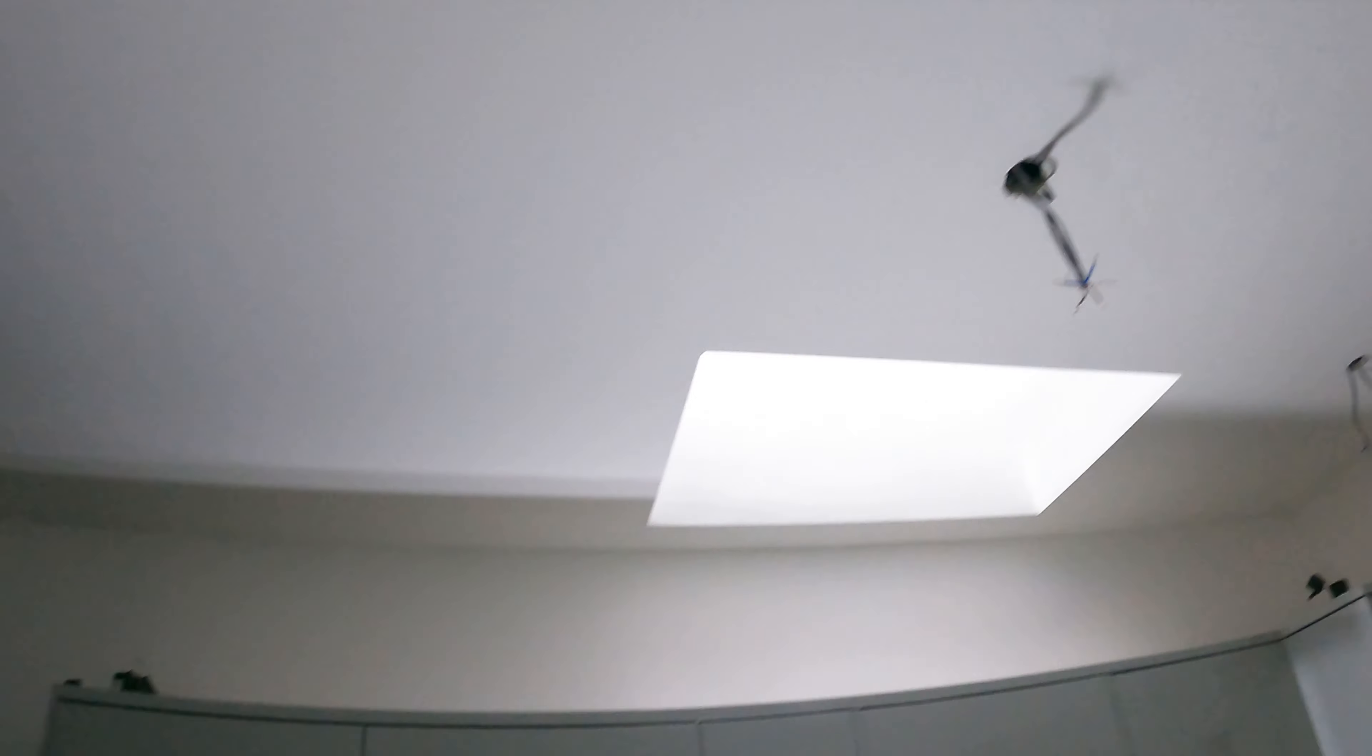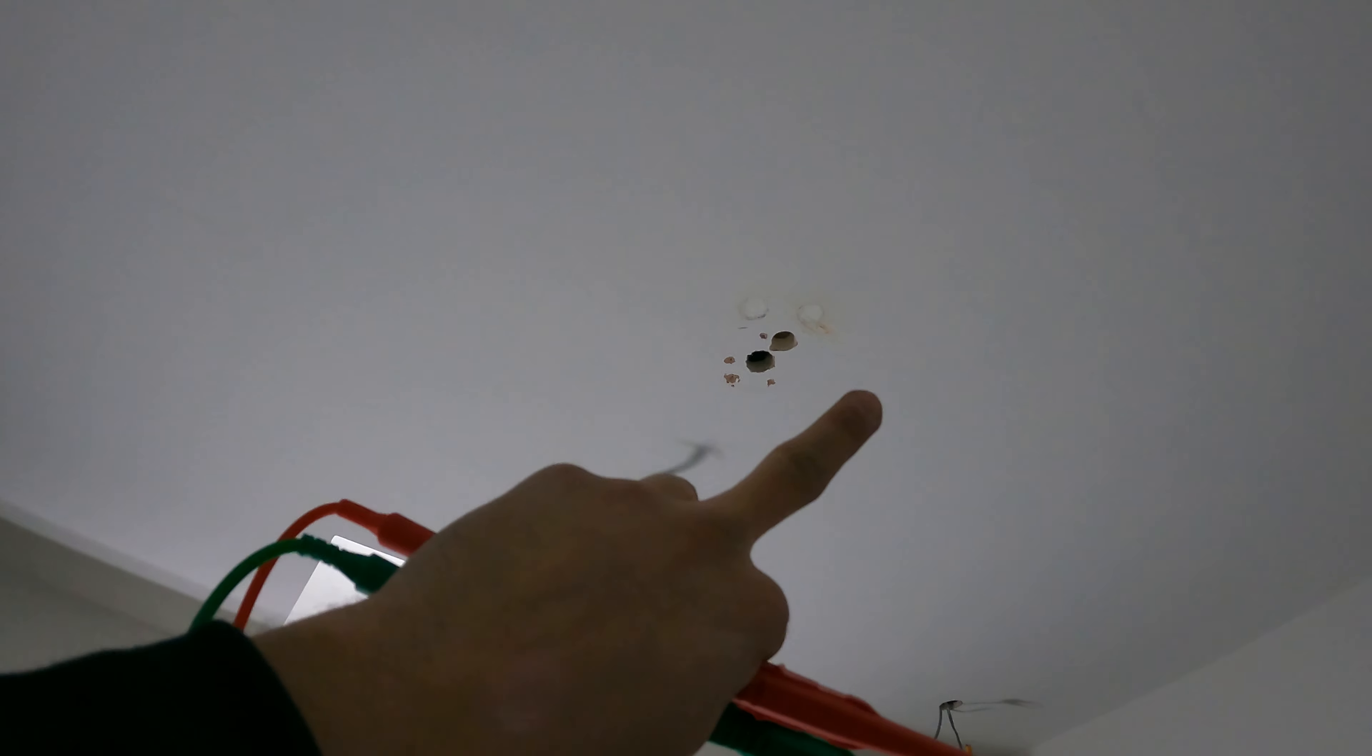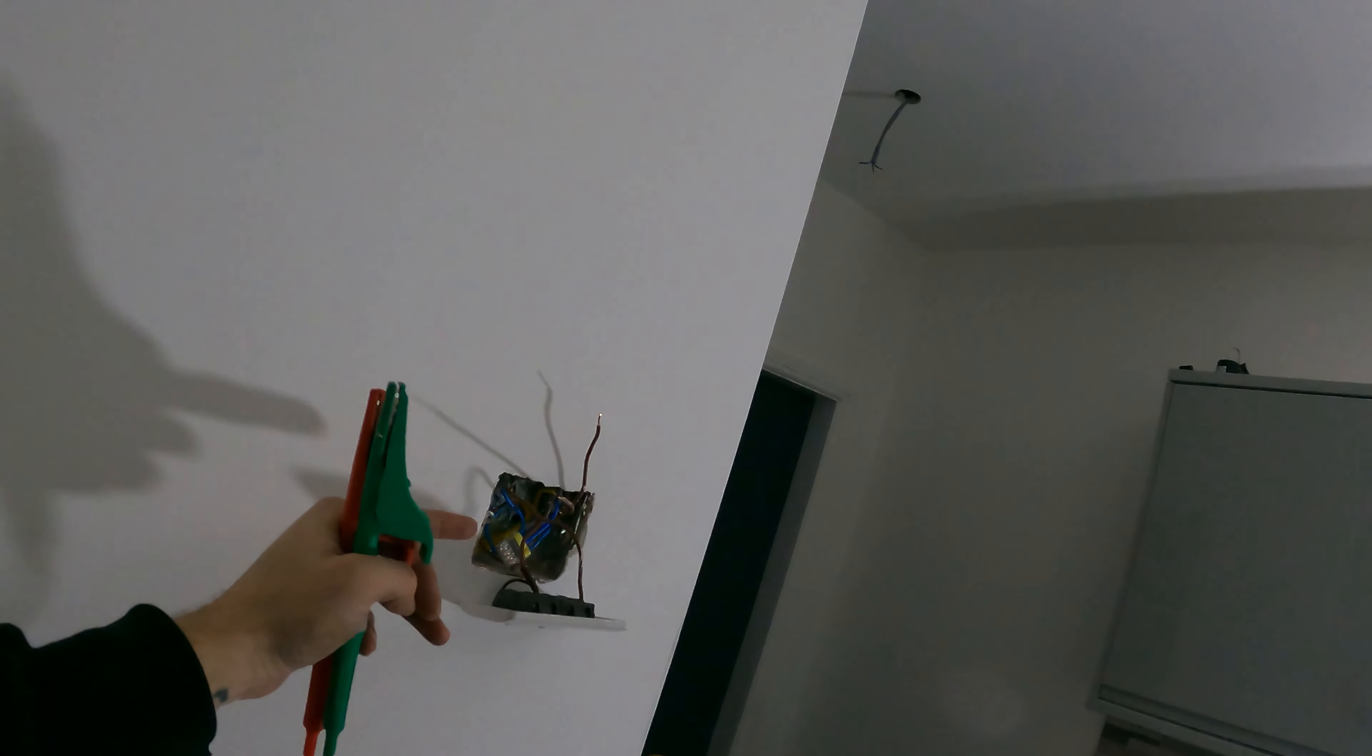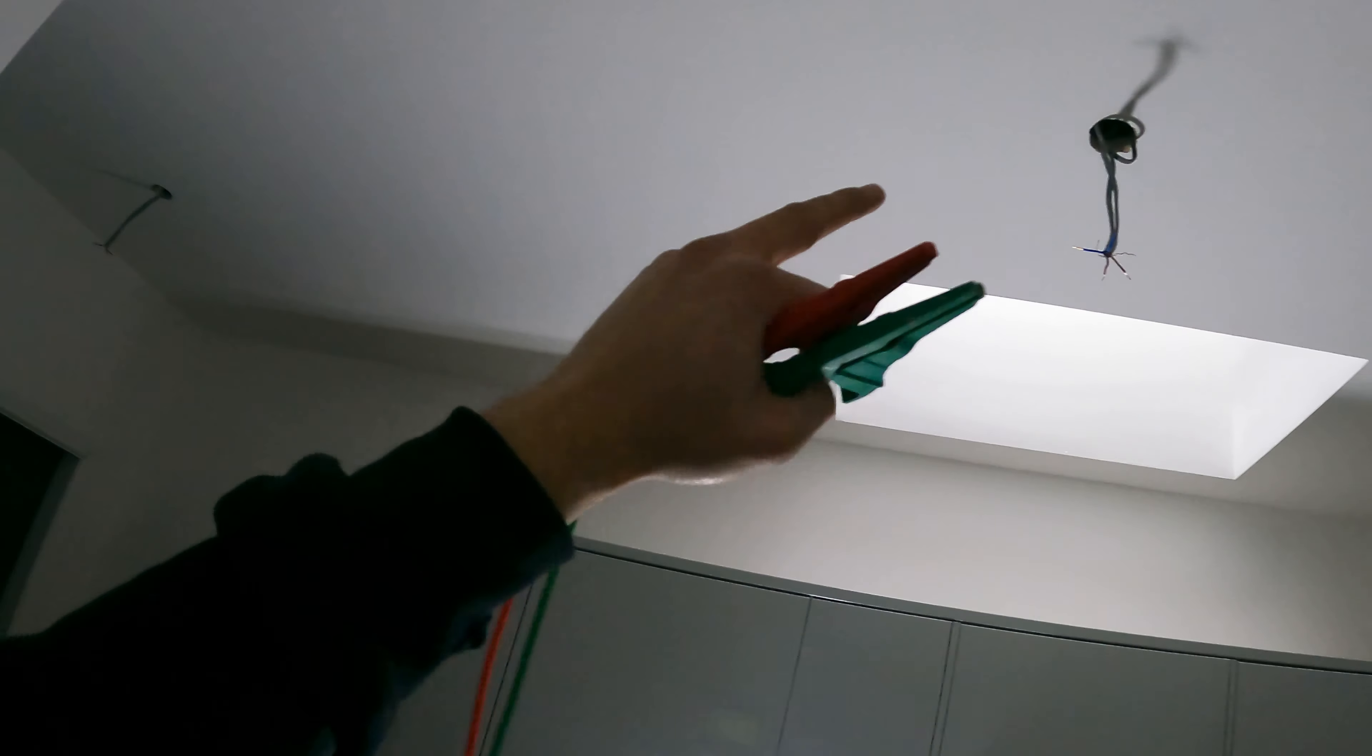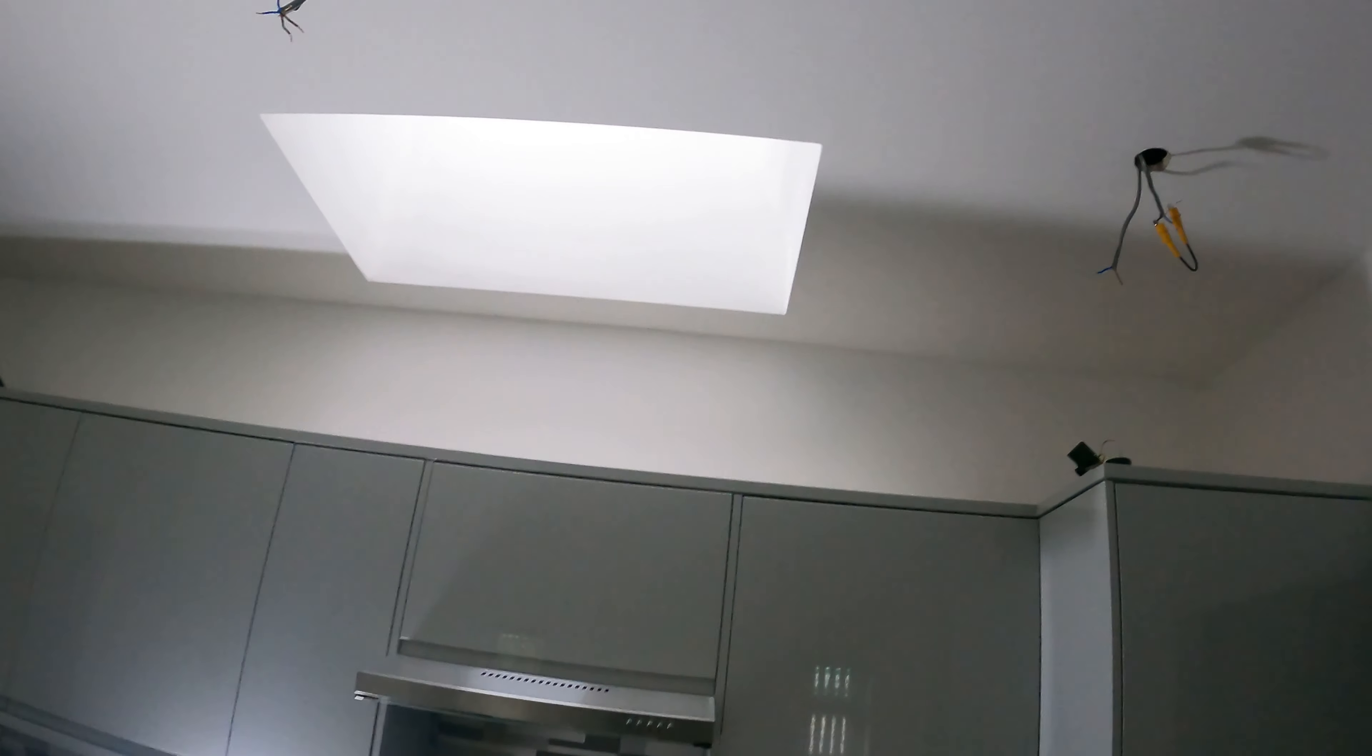Yeah, so what I'm going to do now is I'm going to pull that leg back to here, fish it over to the smoke detector. I'm going to connect it up into the live side—live, neutral, and earth. And then I'm going to reconnect all the lights. So it'll be two cables there, two cables there, and we'll have an end of line as it should be.